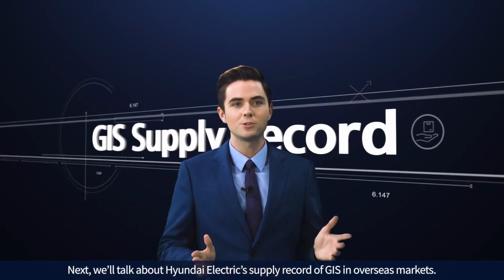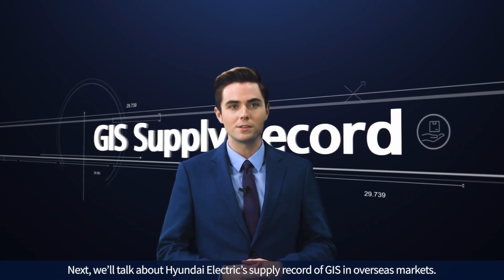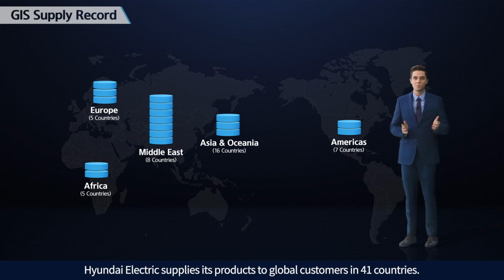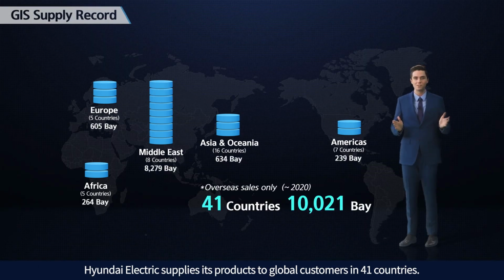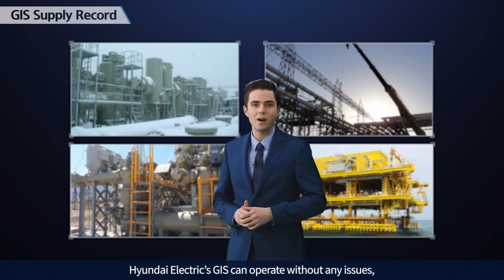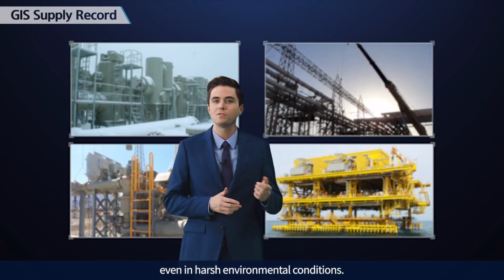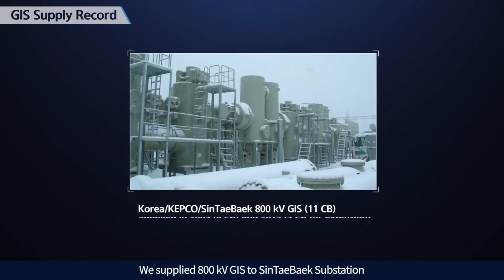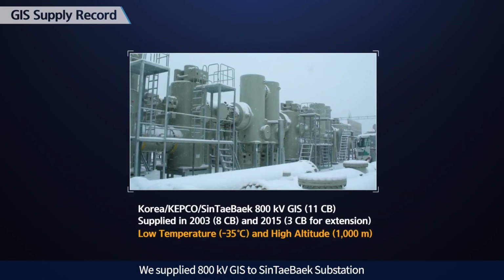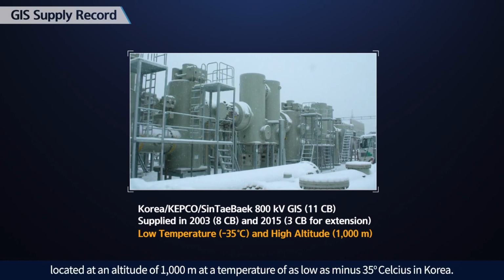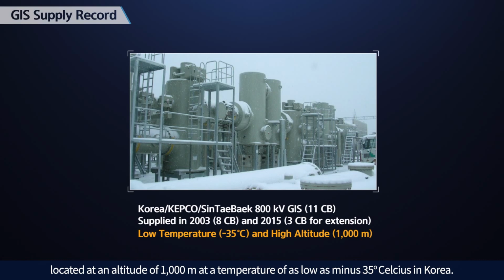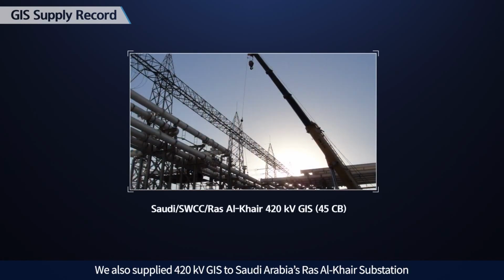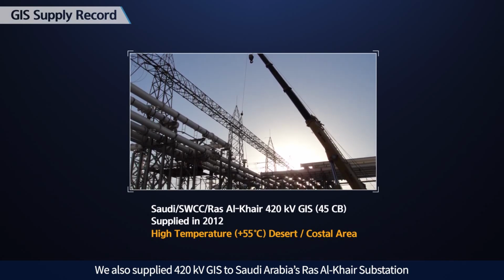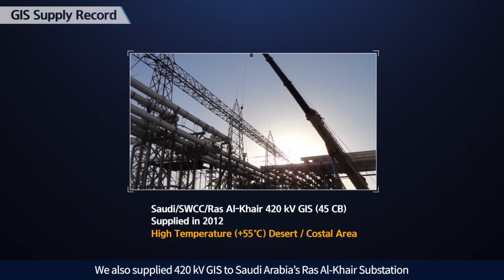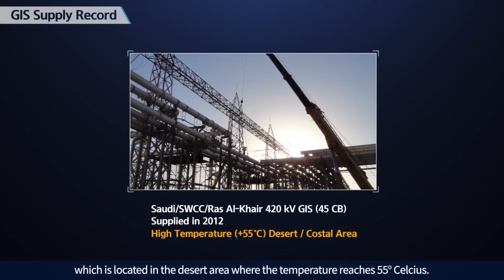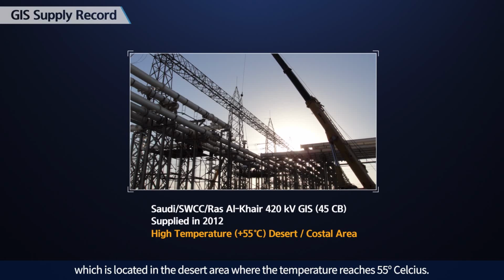Next, we'll talk about Hyundai Electric's supply record of GIS in overseas markets. Hyundai Electric supplies its products to global customers in 41 countries. Hyundai Electric's GIS can operate without any issues, even in harsh environmental conditions. We've supplied 800 kV GIS to Shin-tae-baek substation, located at an altitude of 1,000 meters, at a temperature as low as minus 35 degrees Celsius in Korea. We have also supplied 420 kV GIS to Saudi Arabia's Ras Al Khair substation, which is located in the desert area, where the temperature reaches 55 degrees Celsius.